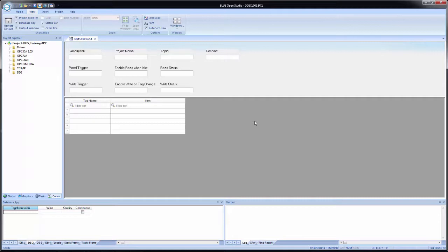These fields are specific for DDE communication. You put in the project name, essentially the server name; the topic, which would be the driver or protocol; and the connect, which is a tag used to start and stop the connection. This is essentially a disable field — they just named it differently for DDE communication. Since we are going to connect to KEPware, I'm simply going to enter in what is required, which I was able to figure out via the help files for KepServerEX. Depending on what SCADA system or application you're using that supports DDE, these settings may be different.